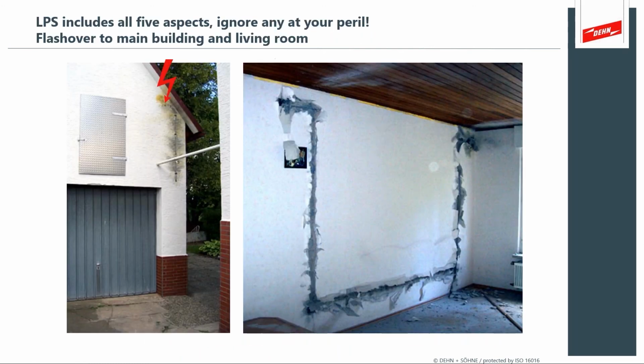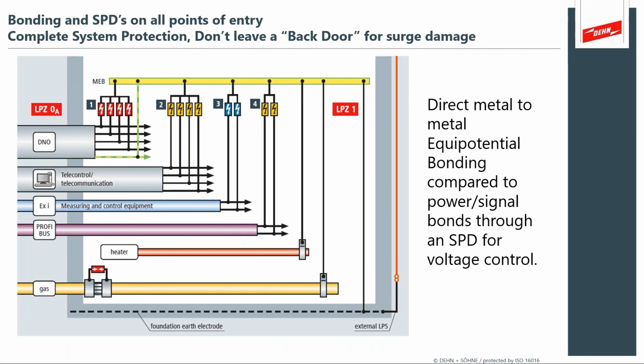And remember, lightning protection systems include all 5 aspects of that pillar of protection. And if you ignore any of them, you run the risk of flashover into your electrical systems. And that brings us to bonding and SPDs. So what is an SPD? What does it do? Well, what an SPD does is it provides electrical bonding through the SPD for voltage control. So direct metal to metal provides equipotential bonding, equal voltage. Well, that is essentially controlling the voltage so that you don't have sparks between your metal elements.